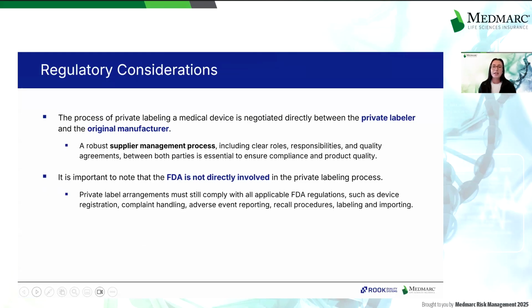The process of private labeling a medical device is negotiated directly between the private labeler and the OEM. As a result, a robust supplier management process, including clear roles, responsibilities, and quality agreements between both parties, is essential to ensure compliance and product quality. It is important to note that the FDA is not directly involved in the private labeling process. However, private label arrangements must still comply with all applicable FDA regulations, such as device registration, complaint handling, adverse event reporting, recall procedures, labeling, and importing.